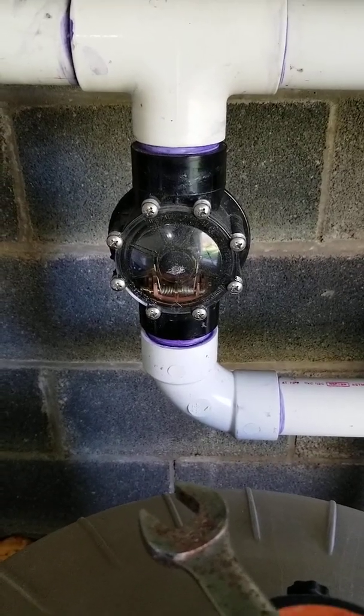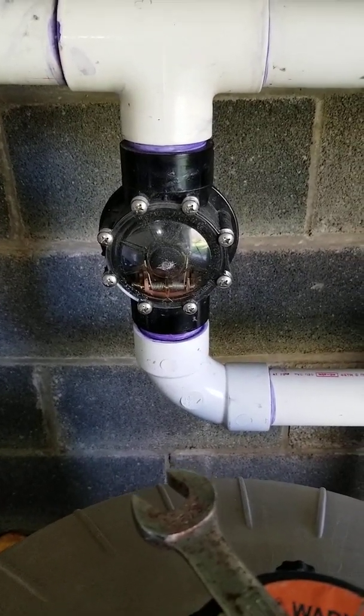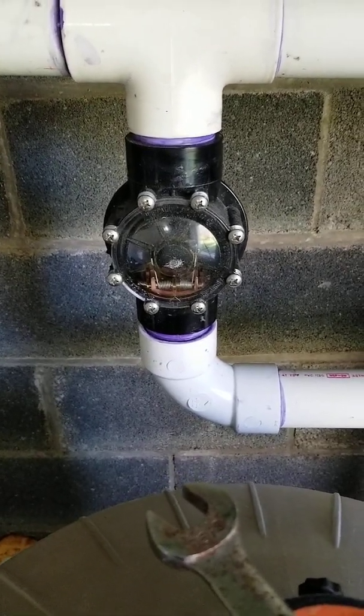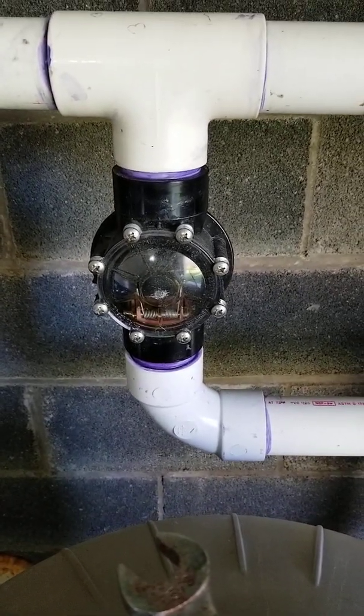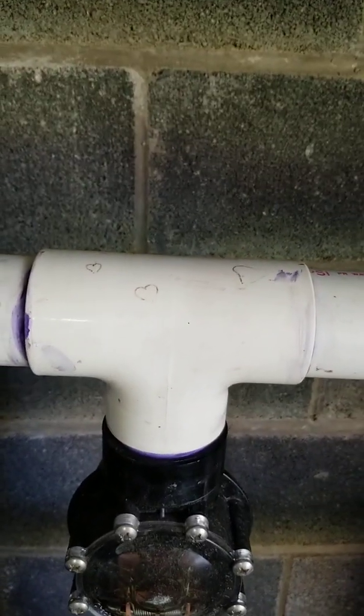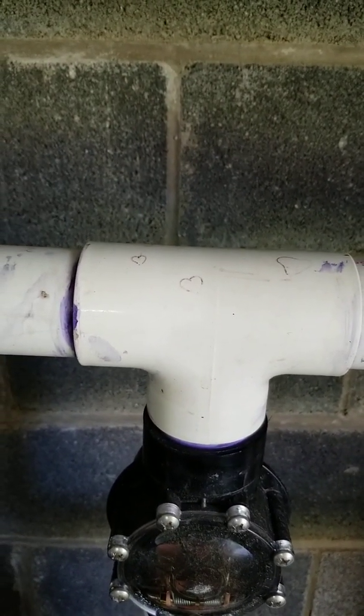I come up into my swing check valve, a 2-inch swing check valve. There is some data for swing check valve. I don't know how valid it is for this particular one, but it's the best information we have, so let's go with it. So treat this as a swing check, 2-inch. I go straight into a 2-inch T. I have branch flow to the left. After that, I have my chlorinator.